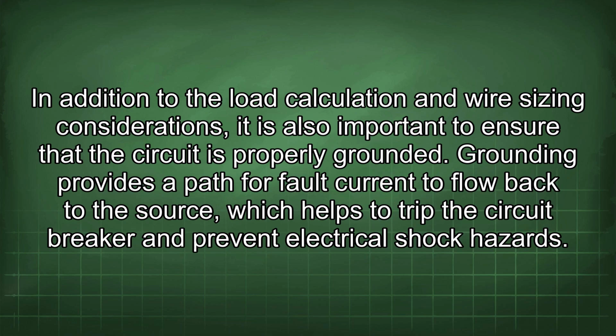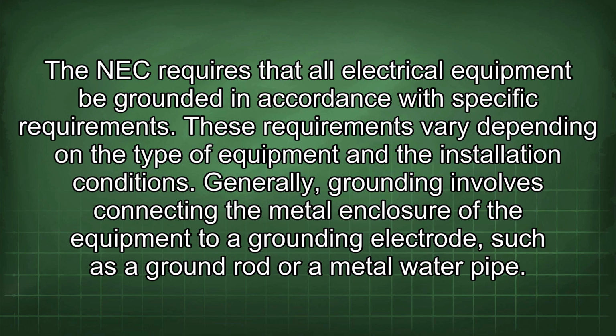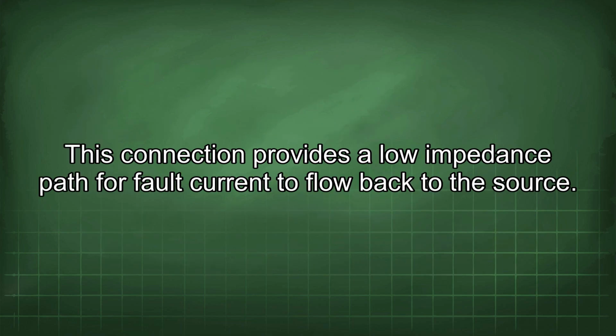In addition to the load calculation and wire sizing considerations, it is also important to ensure that the circuit is properly grounded. Grounding provides a path for fault current to flow back to the source, which helps to trip the circuit breaker and prevent electrical shock hazards. The NEC requires that all electrical equipment be grounded in accordance with specific requirements. These requirements vary depending on the type of equipment and the installation conditions. Generally, grounding involves connecting the metal enclosure of the equipment to a grounding electrode, such as a ground rod or a metal water pipe. This connection provides a low impedance path for fault current to flow back to the source.